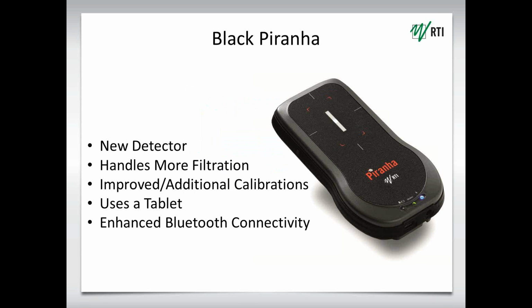Well, it's a new detector technology in it. What does that do for us? It can handle more filtration. We can measure up to the equivalent of 90 millimeters of aluminum or almost 2 millimeters of copper and make sure you don't have any strange kV readings or dose readings. We've improved all the calibrations. We've added many additional calibrations, standard for mammography.